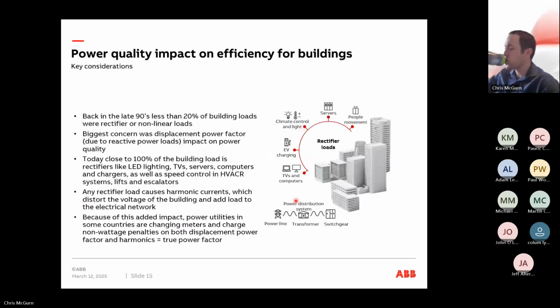So this is a little bit about power quality impact on efficiency for buildings. This is about harmonics. I'm not sure how popular harmonics are in the HVAC industry. It's a big word in the utilities, and we tend to focus on it quite a lot in some of the utility pumping stations used on water sites. They tend to use very big motors, maybe 500 kilowatt and above, that are running all the time.